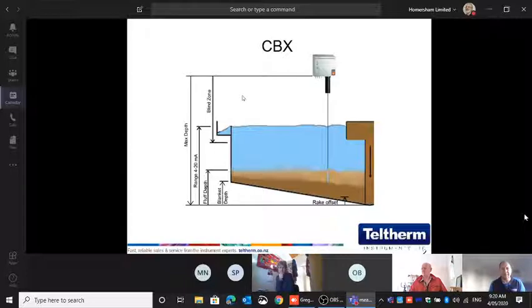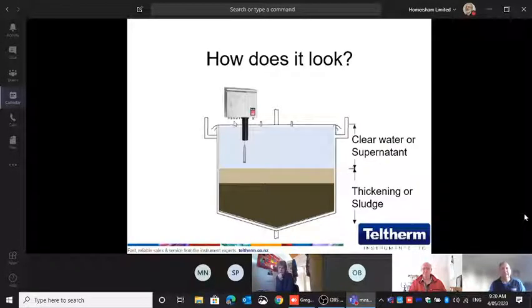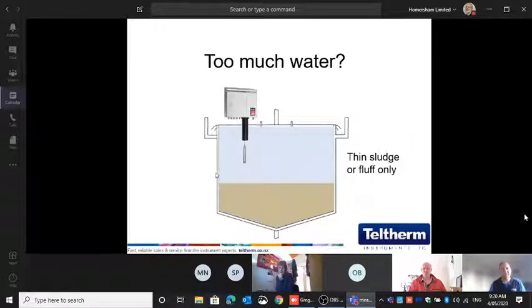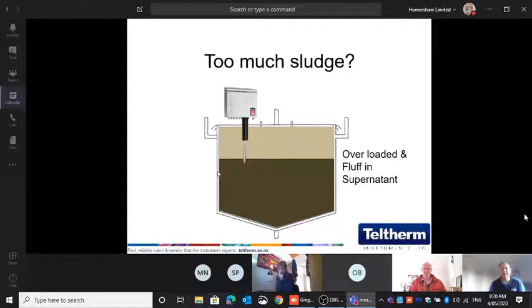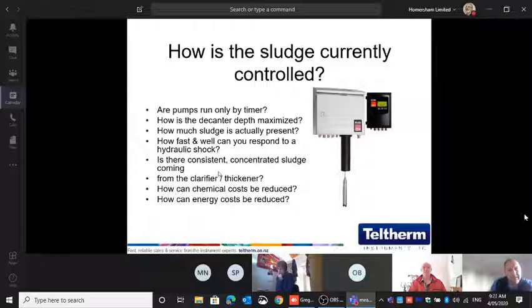So the sludge blanket system basically is what we call a yo-yo sensor. The sensor sits in here, goes down, measures whatever you need to measure, sludge, fluff, and goes back up. While it does that, it sprays water onto the sensor when it goes down, basically to wet the sensor. And when it goes up, it sprays the cable and the sensor clean as soon as it's in there. This is basically what you want to see. This is what you basically, yeah, that's not very good. And this is, well, this is very bad. The problem at the moment is that most people use pumps that run only on a timer. So you don't really know if you're pumping out water or actually sludge. So the unit is not very cheap, because we're looking at around $18,000 for the complete system. But you can reduce your cost very rapidly, mainly energy and chemical costs.